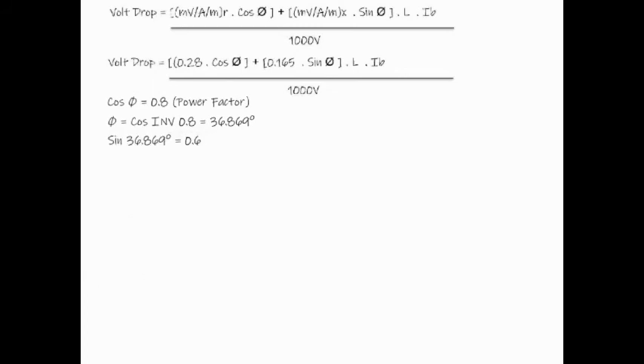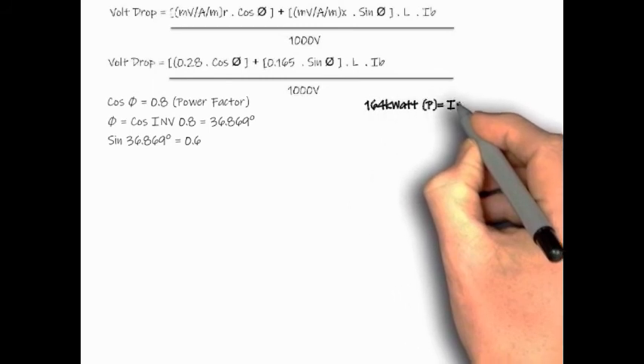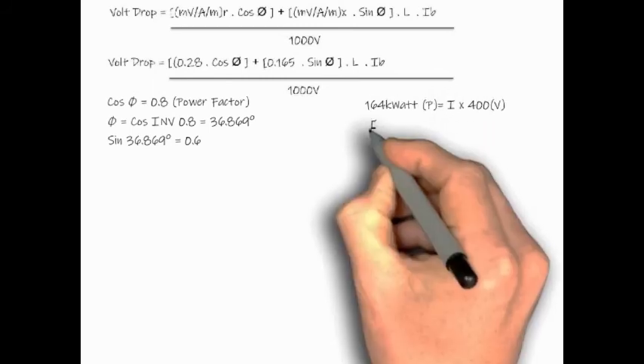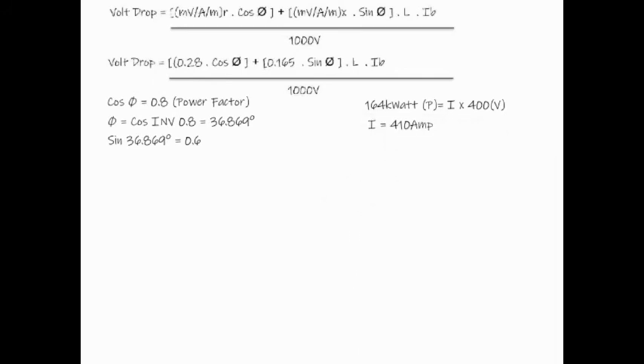Next, I notice my current is not indicated, but we have the power value of 164 kilowatts. Formula to calculate power is P equals IV. If I were to divide my 164 kilowatts by 400 volt supply, using the 164 kilowatts divided by 400 will give me 410 amps.